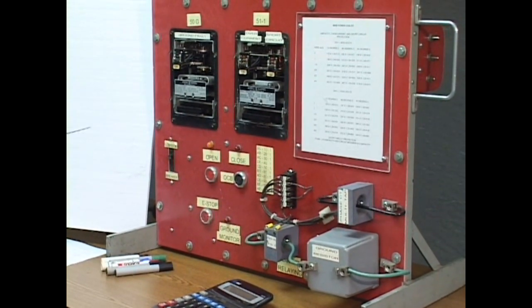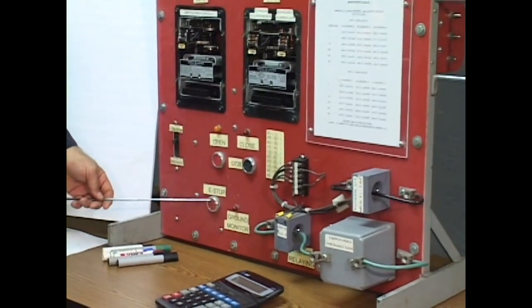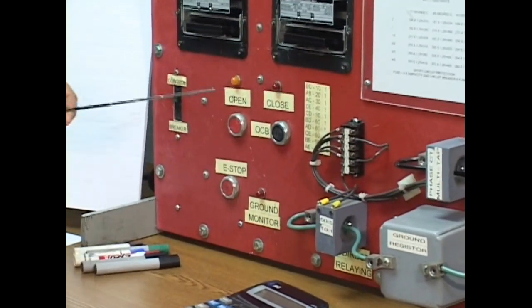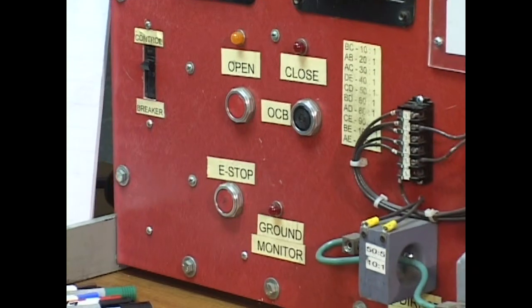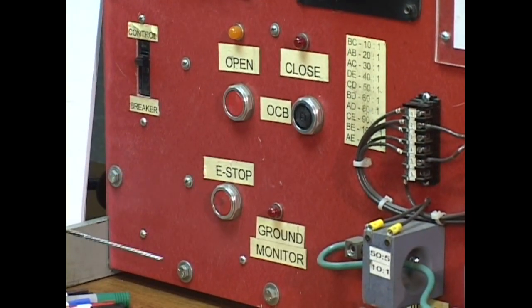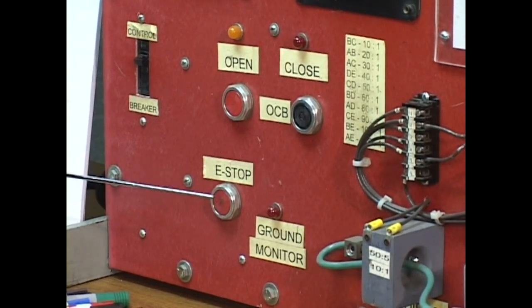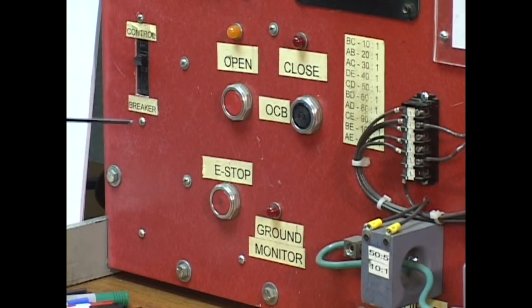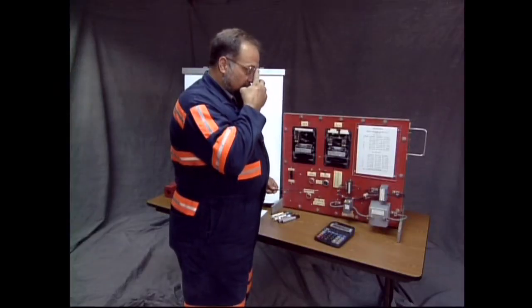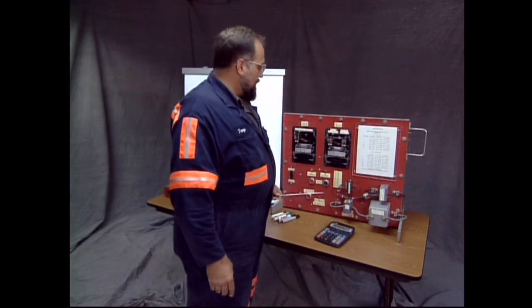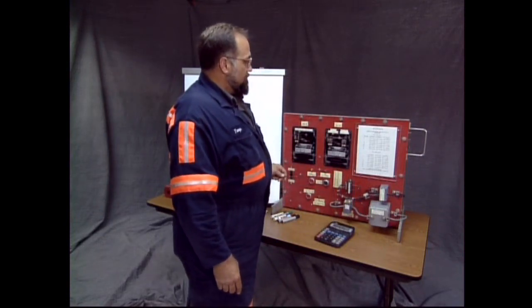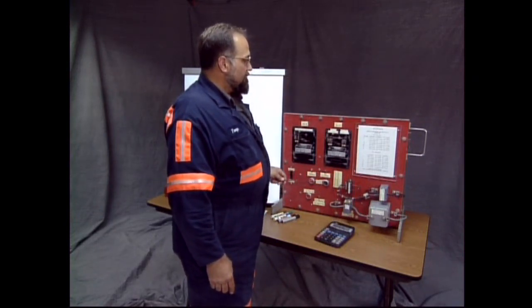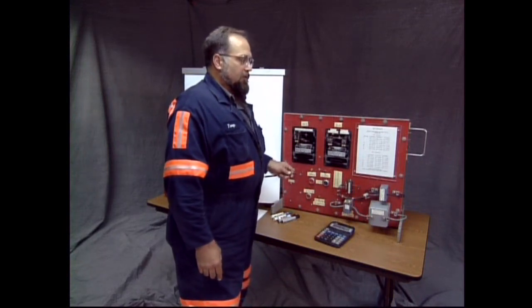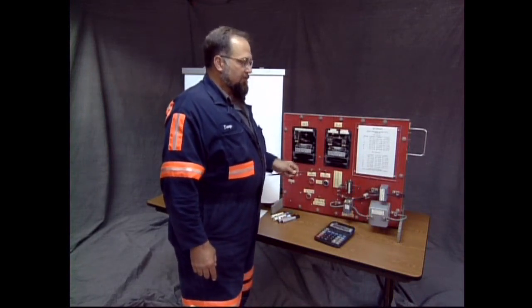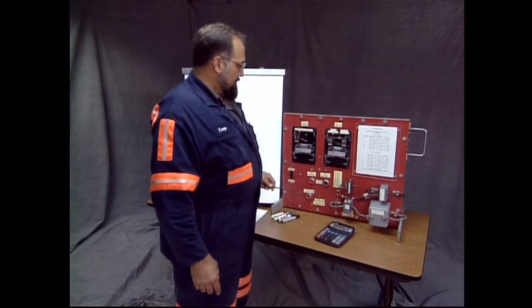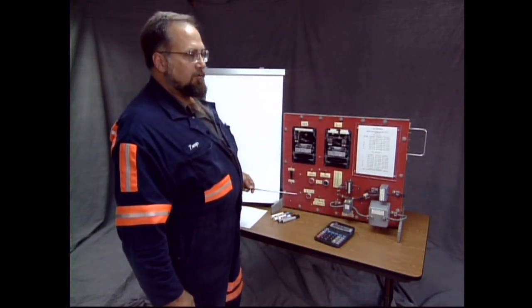As you can see, we also have a button. It's called an E-stop. Some stations have an E-stop present on the control board. Not all do. But the E-stop is on our underground units at every high voltage installation. You would have a high voltage cable serving a portion of your coal mine being cared for by this breaker. This breaker provides the protection. These relays are adjustable so that you can protect a length of cable, a circuit with this unit, and it will have a ground continuity monitor.